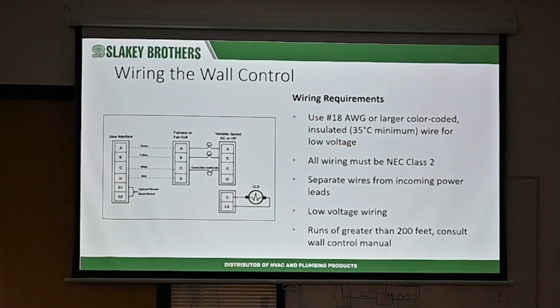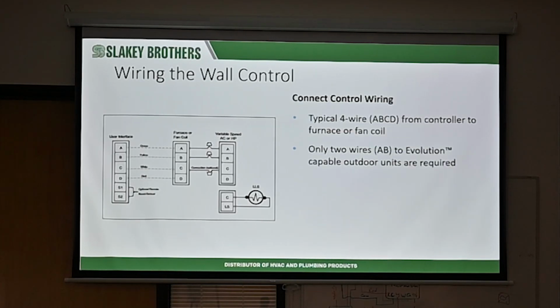We got basic stuff: A, B, C, D. C is optional. Outdoor units got for a long line set. They have on the circuit board for a long line set connection. Very rarely do you really go over 200 feet, but if you ever got one run that's over 200 feet, honestly, I've run into it so little, I don't even know what it is. But you look at the install manual for the wall controller, it tells you what extra little thing you got to do, and it's mainly just put a little resistor between the two communication lines, just to kind of help eat up some of the possible interference that it can pick up on the long run.